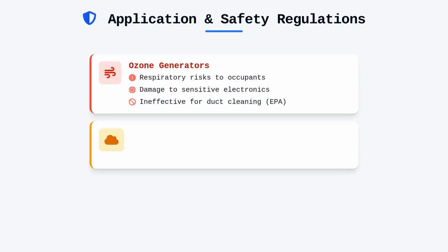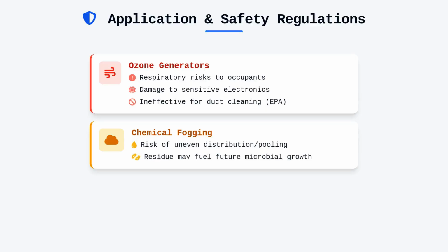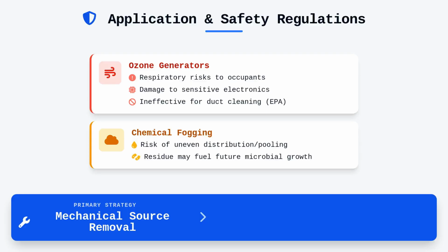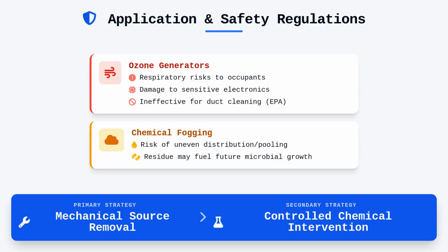Chemical fogging often presents a similarly problematic scenario if the delivery system results in uneven distribution or excessive pooling of liquid within the ductwork, as excess residue can become a medium for future microbial growth rather than a solution to the current one. Always prioritize mechanical source removal over chemical intervention, as the latter should only serve as a secondary strategy in a strictly controlled manner.